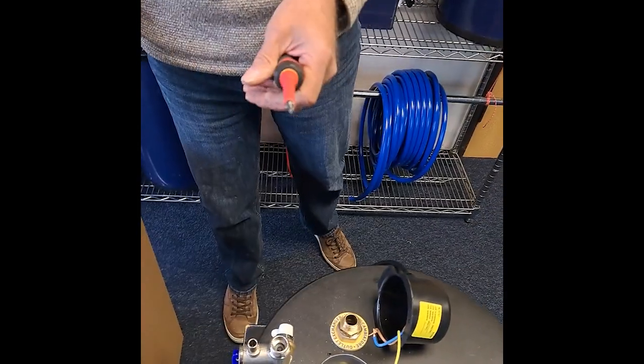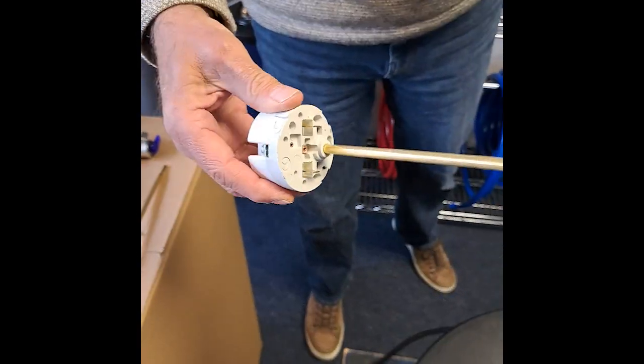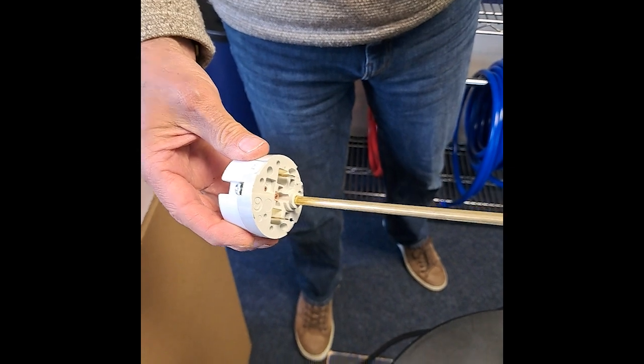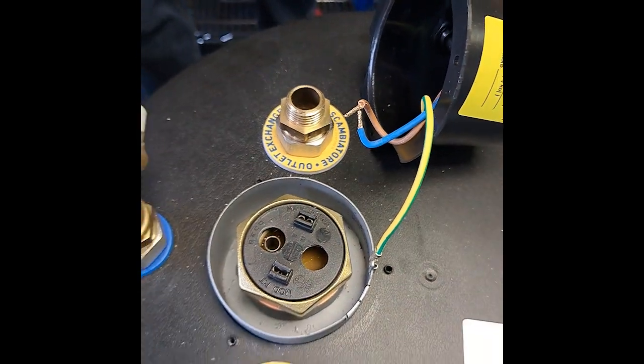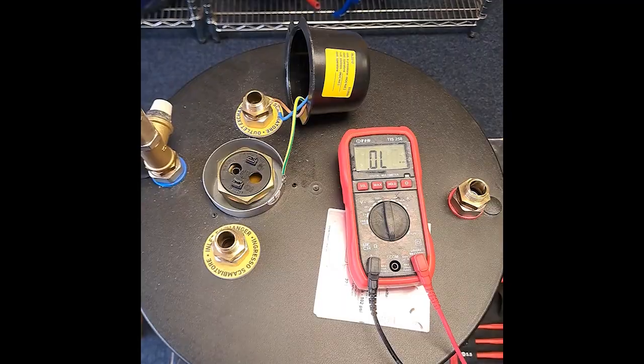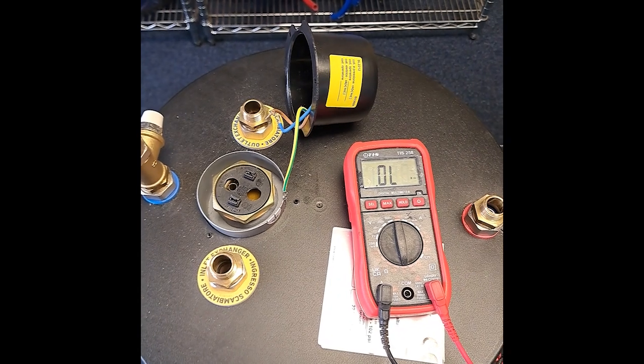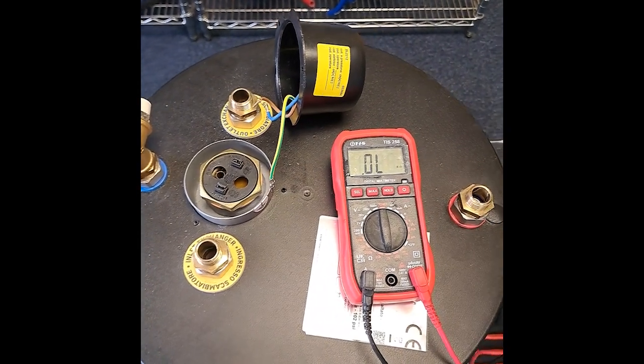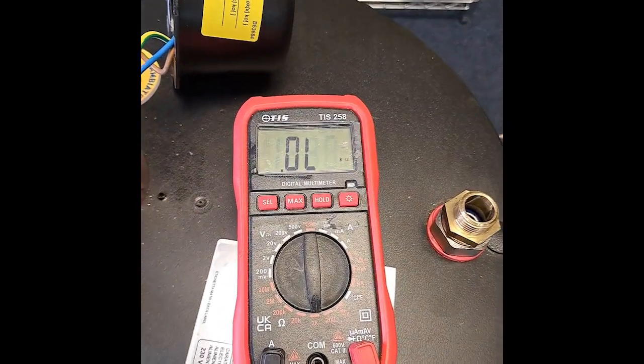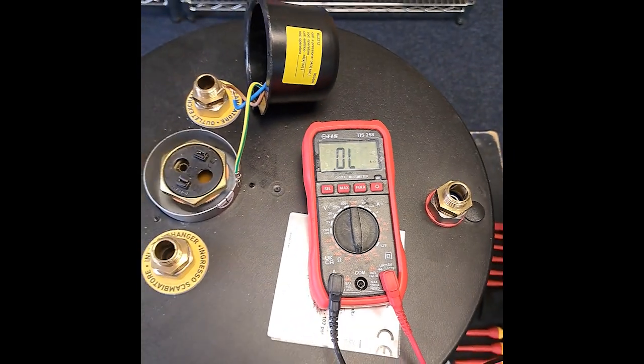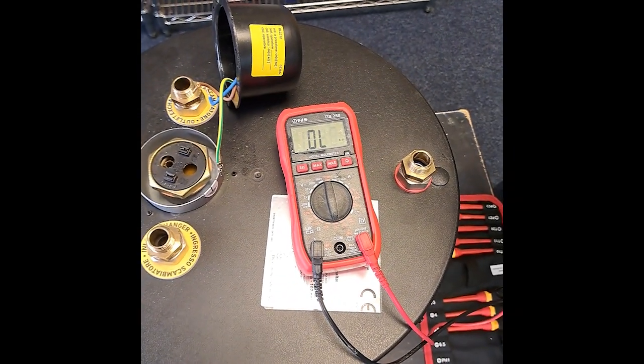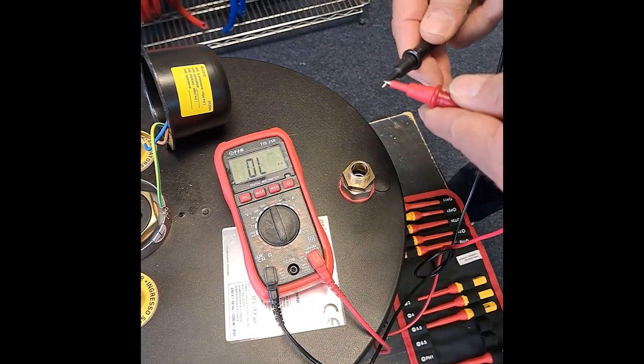So here's the top of the element itself, disconnected from the power supply, and before we remove it, we're going to test it using a simple multimeter. We've set the meter onto ohms to check the resistance in the element. To test the multimeter, we'll touch the ends of the probes together. It's showing a dead short, which means it's working.